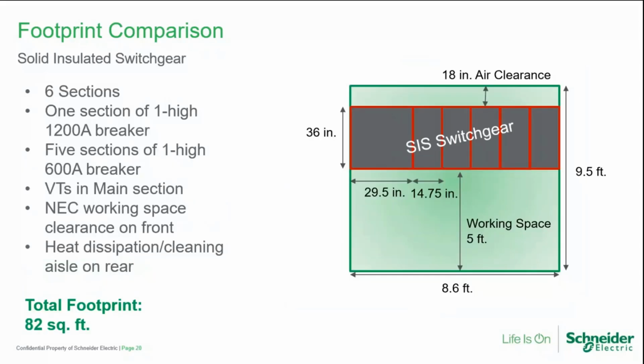If I take this even further and design this with an SIS, again, 6 sections, 1 section for a 1200 amp main, multiple sections here on the end for 600 amp feeders. So being able to get more load appropriate size breakers if I'm using SIS designs or even GIS designs, with the available 600 amp breakers as opposed to only 1200 amps. VT sections below that main breaker, NEC working clearances on the front, heat dissipation and cleaning aisle in the back, looking at 82 square feet of space.